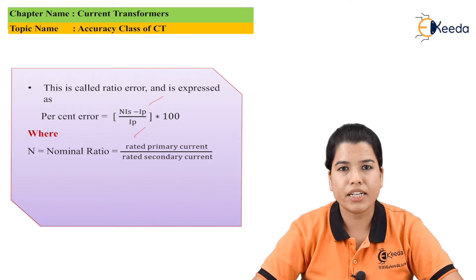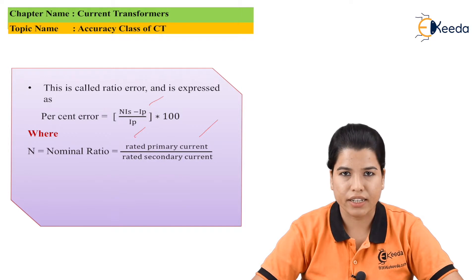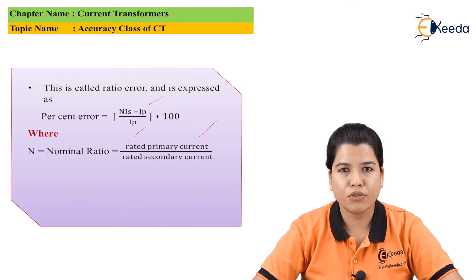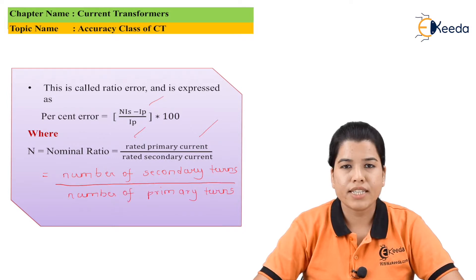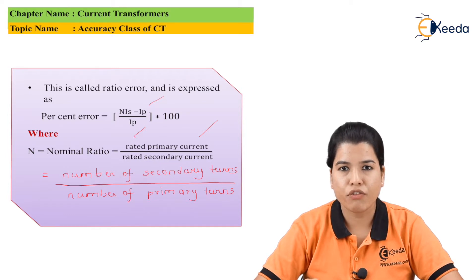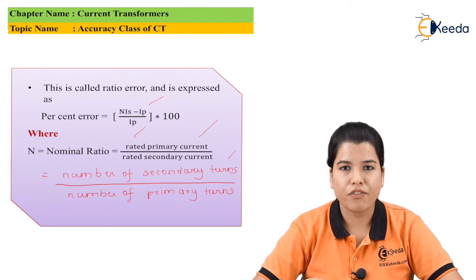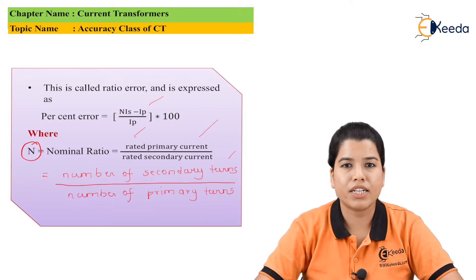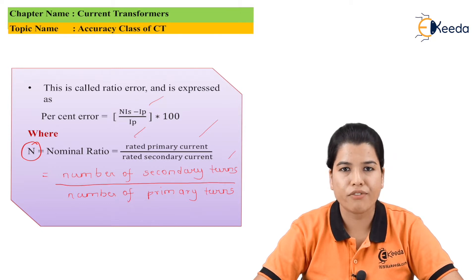Where N is the nominal ratio, which equals rated primary current divided by rated secondary current. N can also be expressed in terms of turns: N equals number of secondary turns divided by number of primary turns. If you compare N — the nominal transformation ratio — with the transformation ratio of a regular transformer, you will find it is exactly the reciprocal of the transformation ratio of a regular transformer.